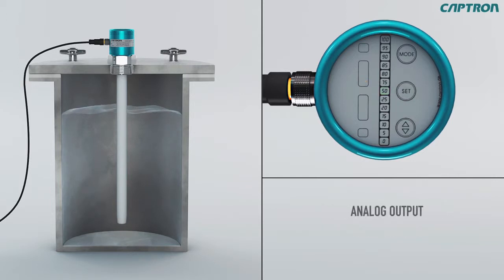To set the analog output, now the A0, A4, and V0 light up in addition to the 0 and 100% displays. Select again with the up-down the desired analog output mode. A0 signifies 0 to 20 milliamperes, A4 signifies 4 to 20 milliamperes, and V0, 0 to 10 volts. If you touch Set now, the adjusted value will be saved and the probe switches to measuring mode. Now the probe is operational and displays the current fill level.